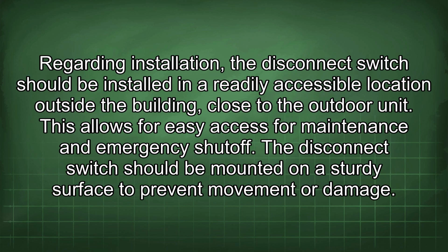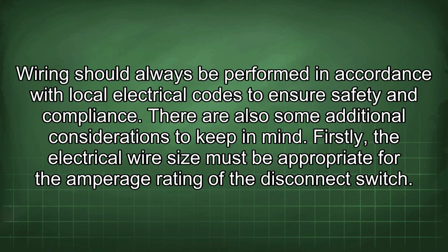Regarding installation, the disconnect switch should be installed in a readily accessible location outside the building, close to the outdoor unit. This allows for easy access for maintenance and emergency shutoff. The disconnect switch should be mounted on a sturdy surface to prevent movement or damage. Wiring should always be performed in accordance with local electrical codes to ensure safety and compliance.